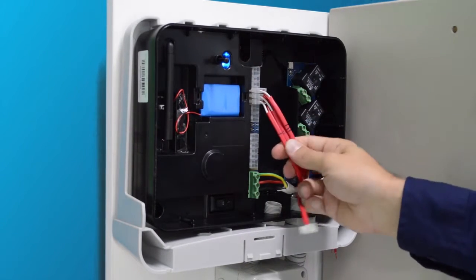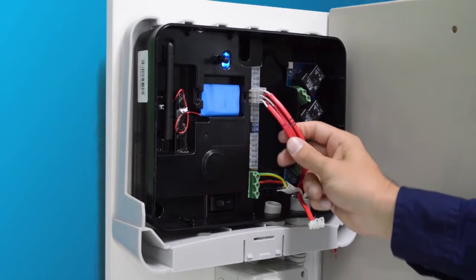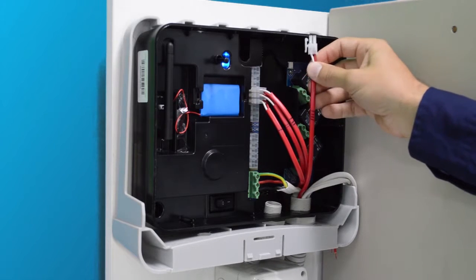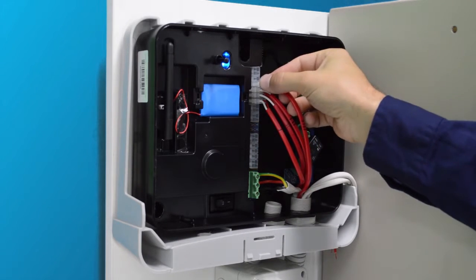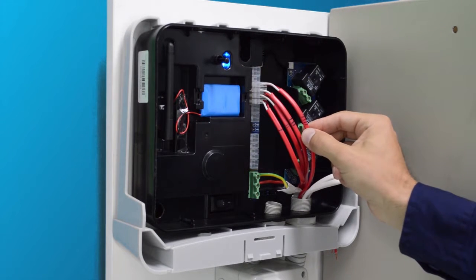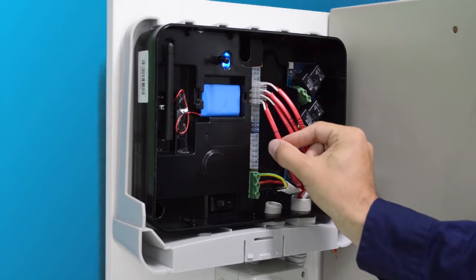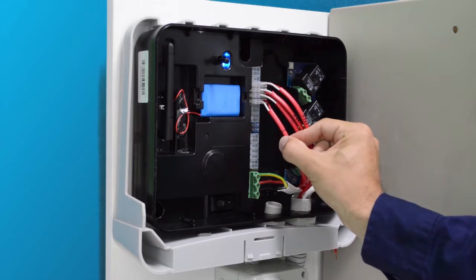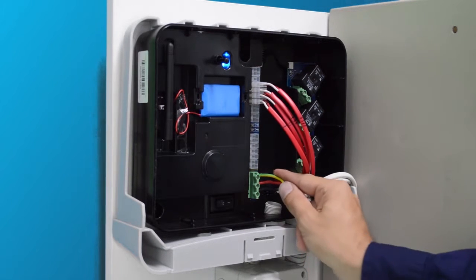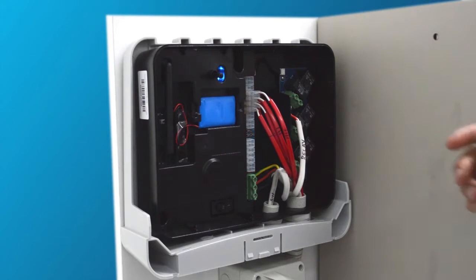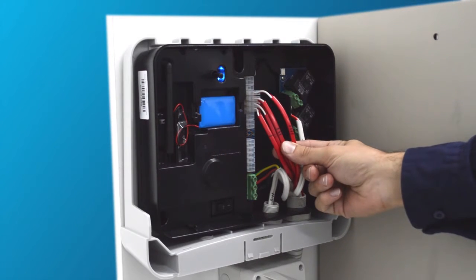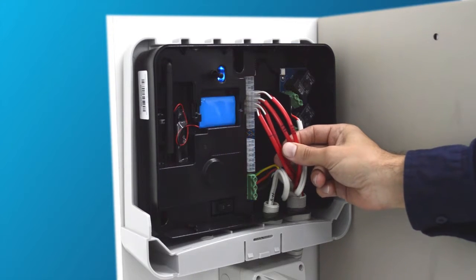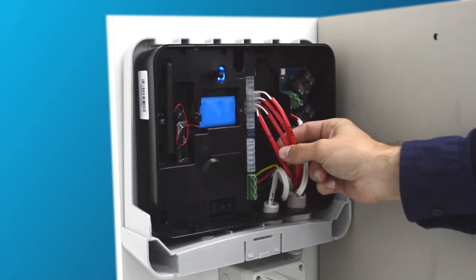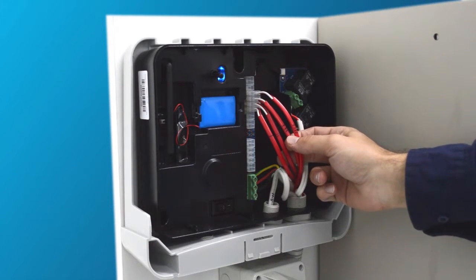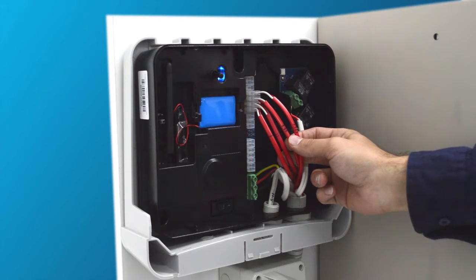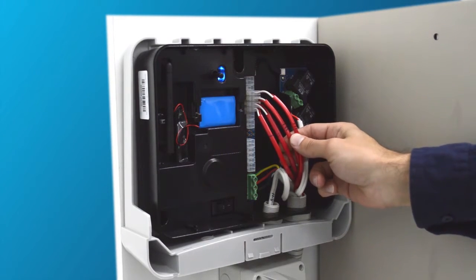It is important that these current clamps match the phase rotation for the mains. Plug the current clamp labelled 4, the solar current clamp, into phase 4. It is important that this solar clamp has been clamped around the same phase as the clamp 1 mains clamp has been clamped around, which is also the same phase that the unit has been powered from. It is important that you install the current clamps in the same order as the phase rotation. If the phase rotation has been measured as standard, you need to install the current clamps in a standard 1, 2 and 3 position. If the phase rotation is non-standard, they must be installed to suit.